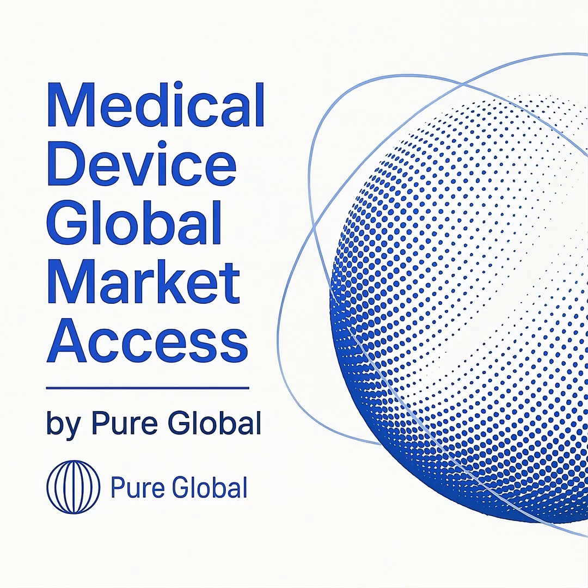The next step is to classify your device according to India's risk-based system, which categorizes products into Class A for low risk, Class B for low-moderate risk, Class C for moderate-high risk, and Class D for high risk. This classification determines the regulatory pathway and the required documentation.